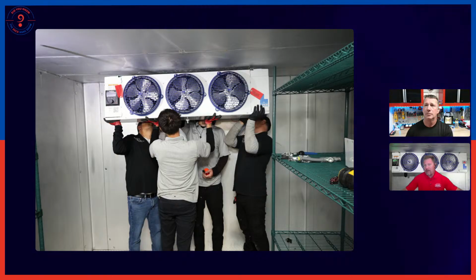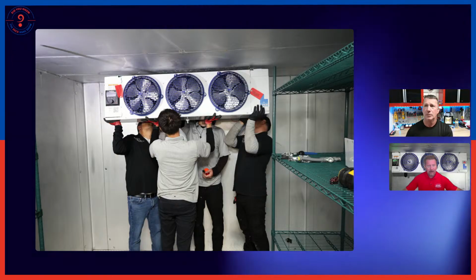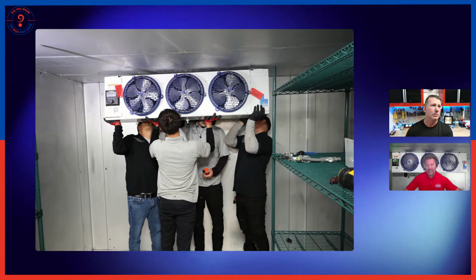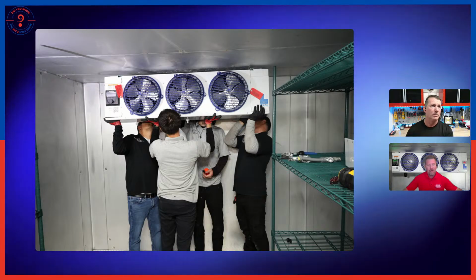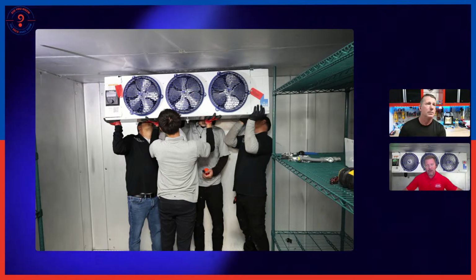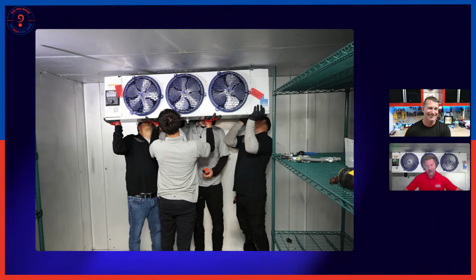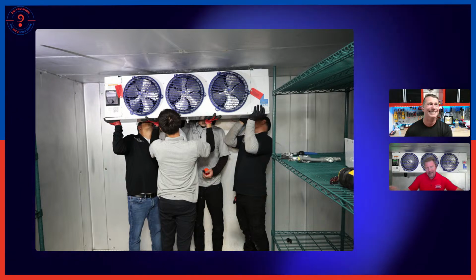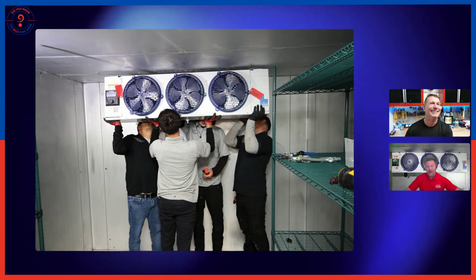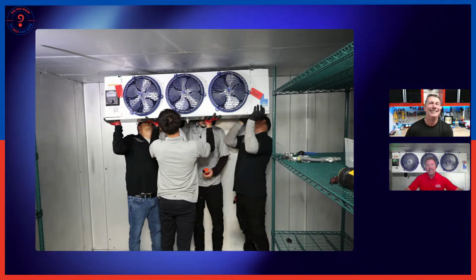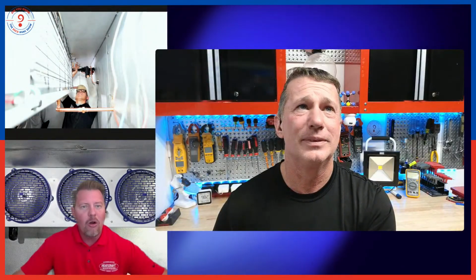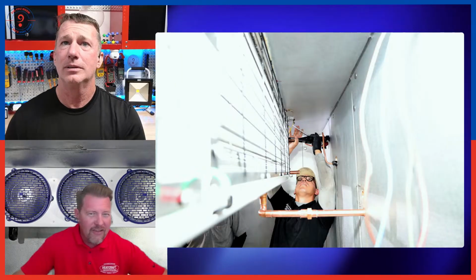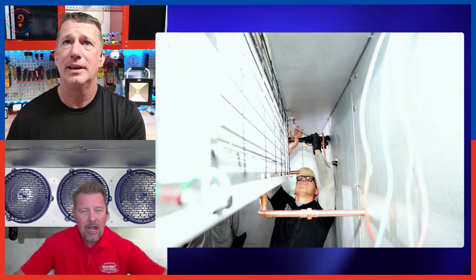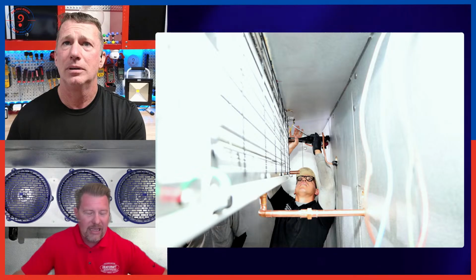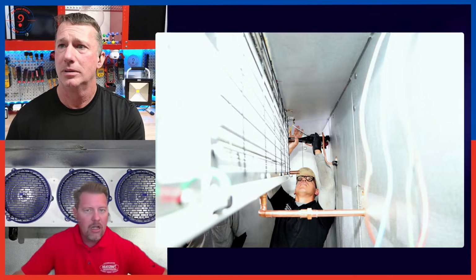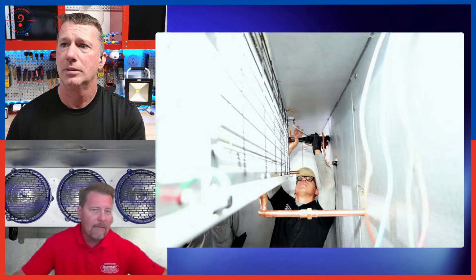Obviously, we as technicians probably know why that's there. Somebody has gone in and seen ice on a coil. I've been called out on a weekend more than once for somebody that de-iced a coil with an ice pick, not knowing that there was a refrigeration coil behind there. Obviously, that grate is not going to 100% prevent that, but it is there as a warning. You can vaguely see it in that picture. But yes, there is a guard on the back of these coils now. All A2L ready coils will have that.